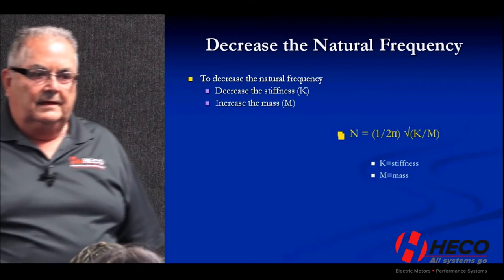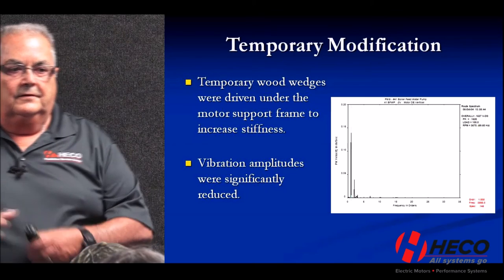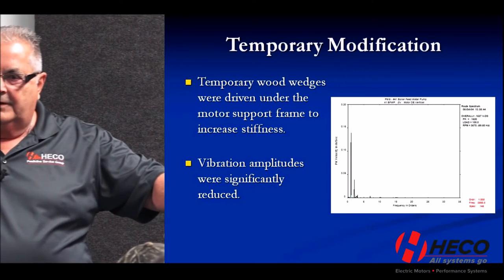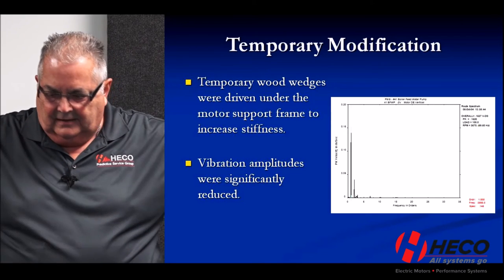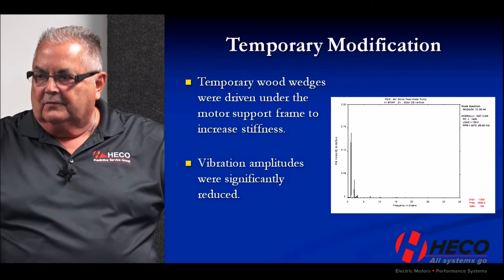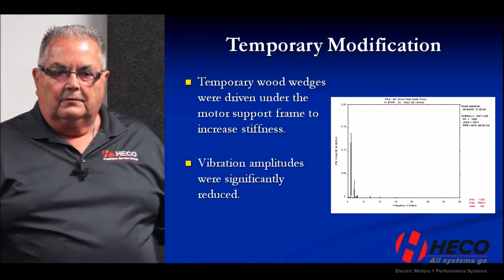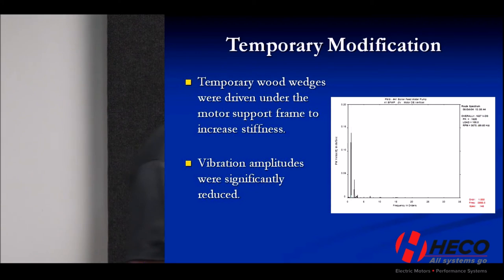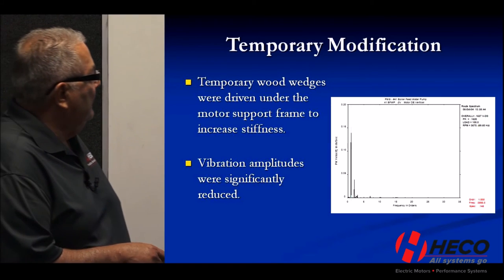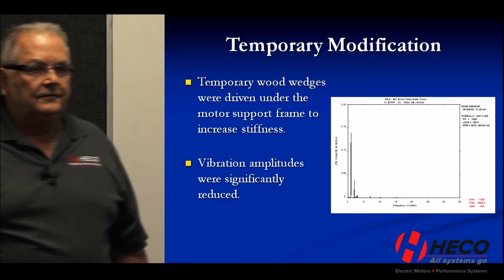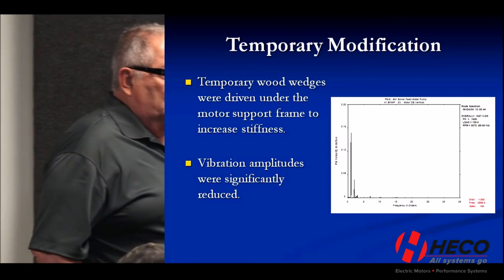What we did was put some temporary wooden wedges and drove them in under the support frame. The setup had a concrete pedestal, two pieces of I-beam, and a piece of channel iron across the top — the motor was bolted down to that channel. All we did was put two-by-four wooden wedges in the center between the channel and the concrete base. The vertical vibration amplitude went from 0.5 inches per second down to about 0.14 inches per second — without ever shutting the motor down. Nothing fancy at all, just wooden wedges.